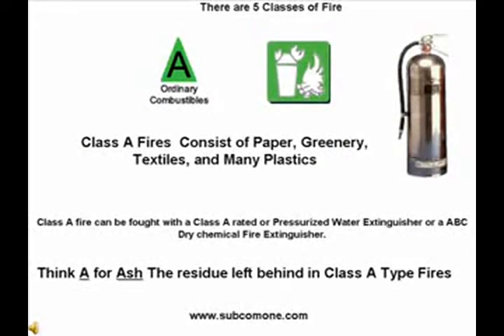There are 5 classes of fire. A class, ordinary combustible fires. Class A fire consists of paper, greenery, textiles, and many plastics. Class A fires can be fought with a Class A rated pressurized water fire extinguisher or an ABC dry chemical fire extinguisher. Think of the letter A for ash, the residue that's left behind from a Class A type of fire.